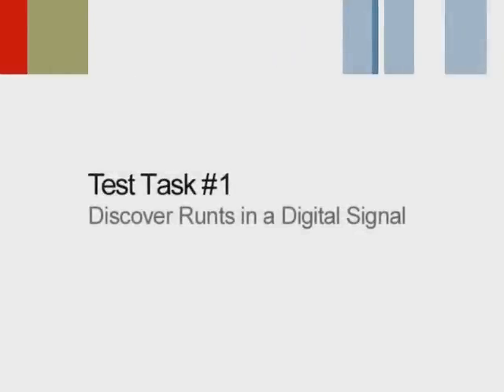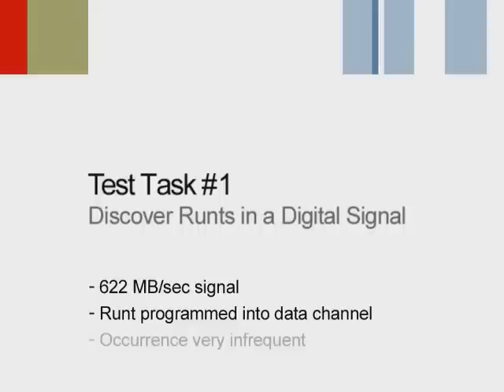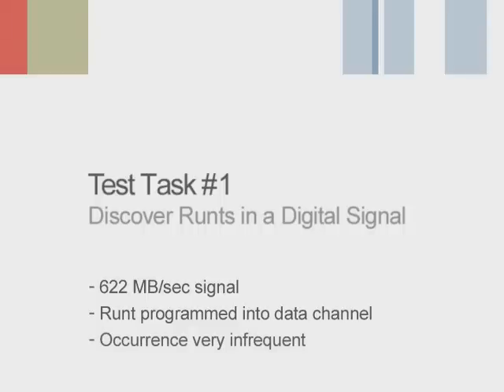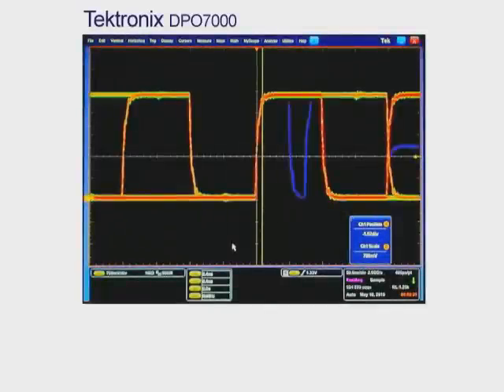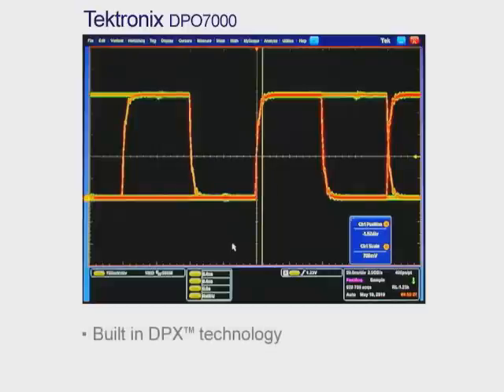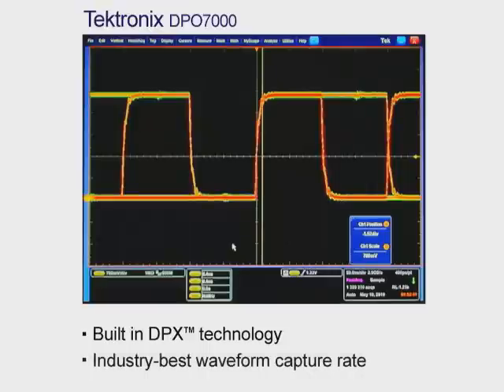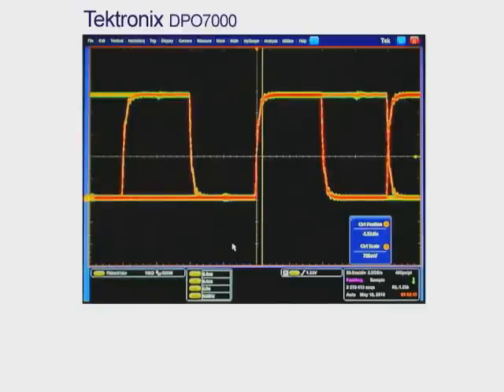The first test task is to discover any runts that may exist in a digital signal. This task uses a 622 megabit per second digital signal with a runt programmed into the data channel. Its occurrence is very infrequent, making identification a difficult task. Here we see how quickly the Tektronix DPO7000 finds the runt pulse on the signal. With the DPO7000's built-in DPX technology providing an industry-best waveform capture rate, you can see just how quickly and easily we're able to accomplish this task.